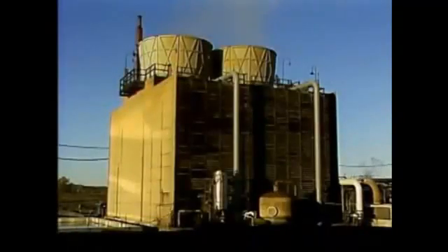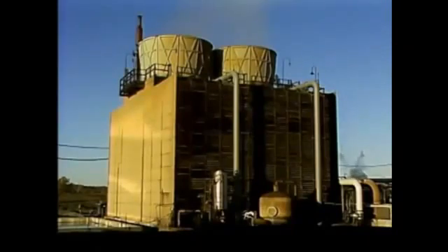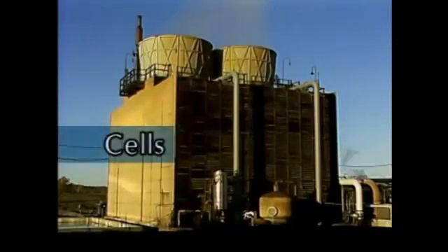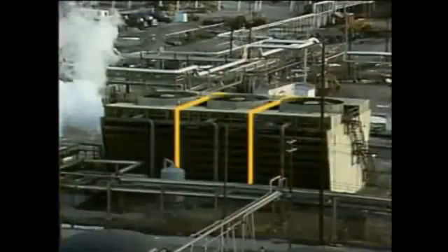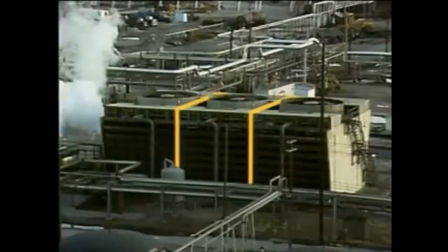Regardless of the type of cooling tower, there are some components that are common to most towers. For example, many towers are divided into sections called cells. This tower has three cells. Each cell contains all of the components of a single tower, except they share a common catch basin. Each cell of a tower can be operated independently, so the proper amount of cooling can be maintained by taking one or more cells out of service or placing them in service.